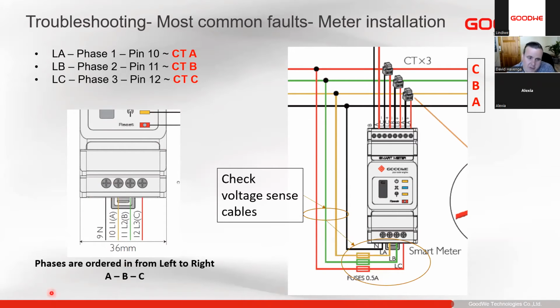It's very important, very important that this is 100% correct for the 3-phase installations. And as I said, if you change the phases on the inverter for a phase rotation error, then you're going to have to change the phases as well as swap the CTs around. So just pay careful attention to that.